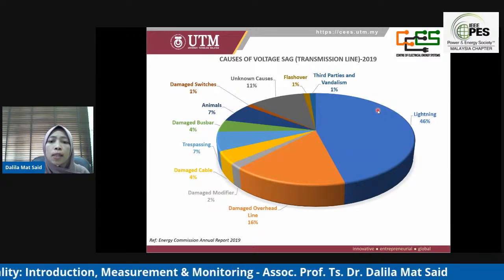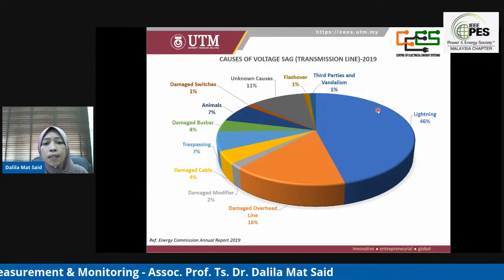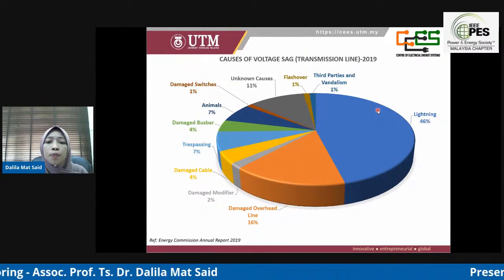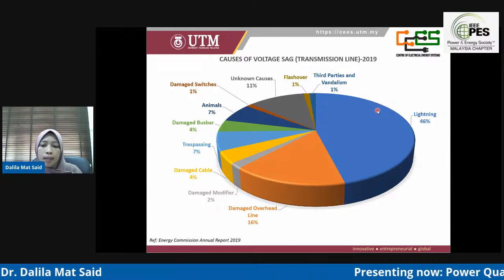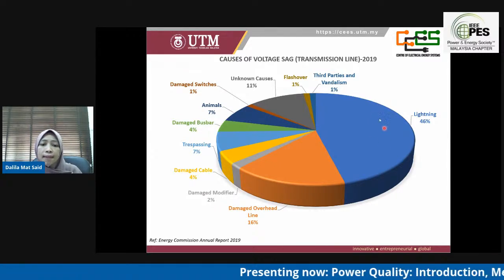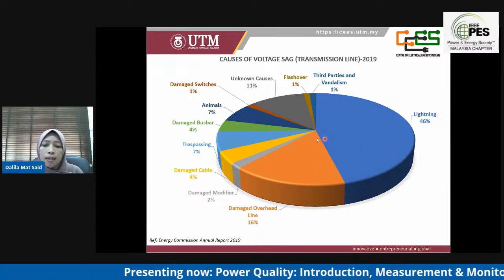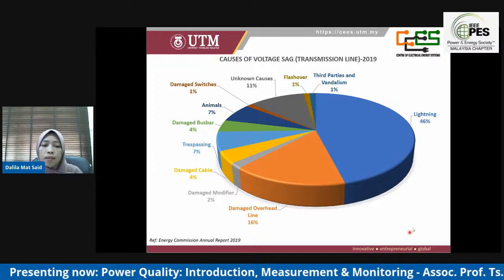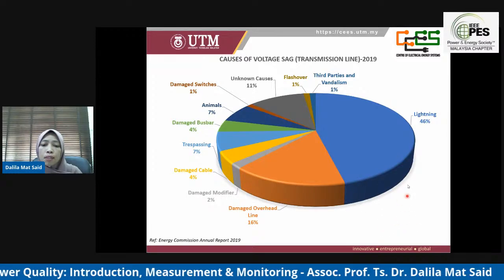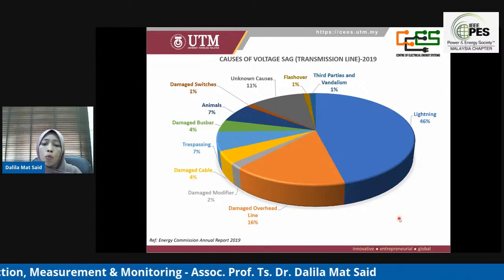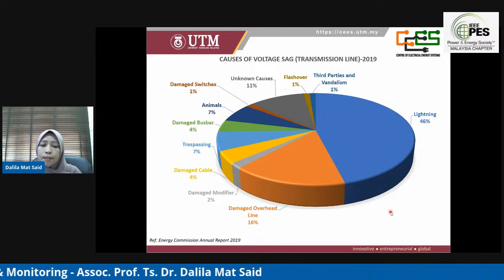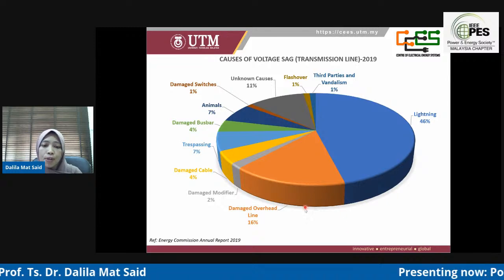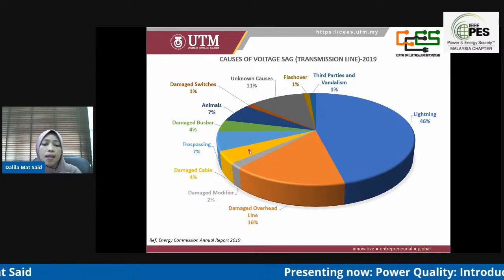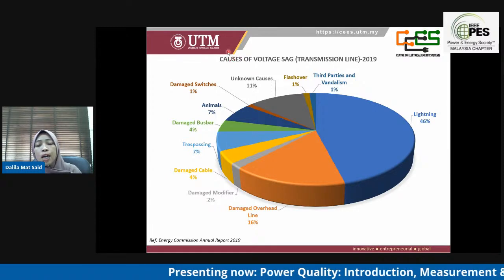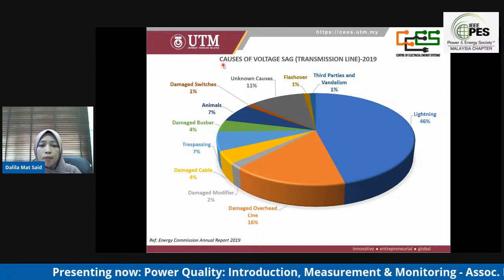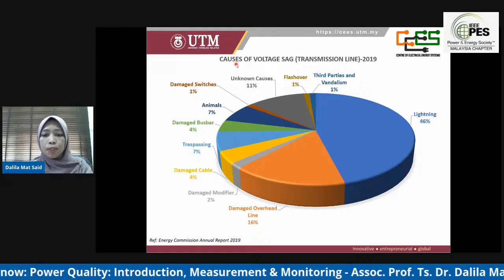So next, we see what the factors contributing to this event are. This is the cause of voltage sags at the transmission line, and we can see that the highest contribution and primary cause of voltage sags on the transmission line was lightning strike, followed by damaged overhead lines at 16%, and unknown causes at about 11%. That's the cause of voltage sags at the transmission line.